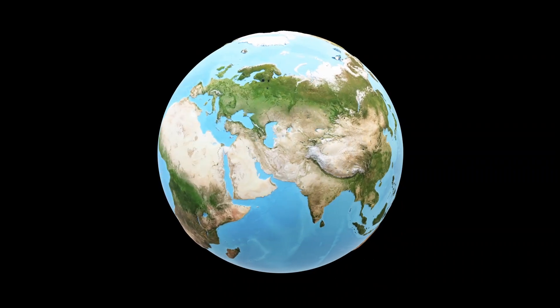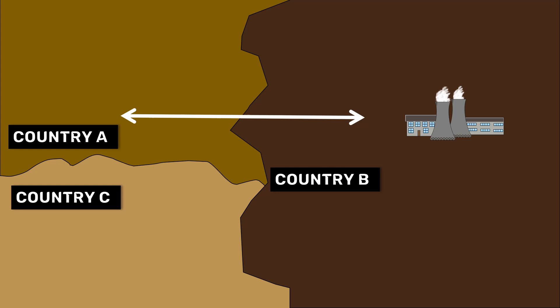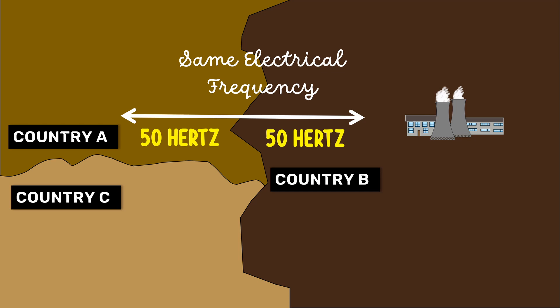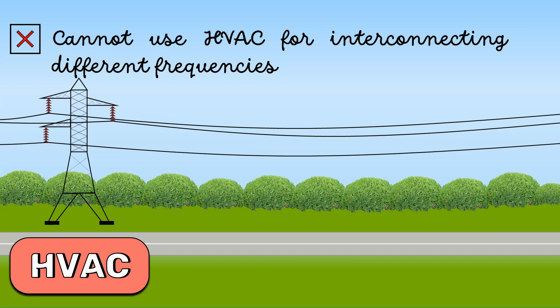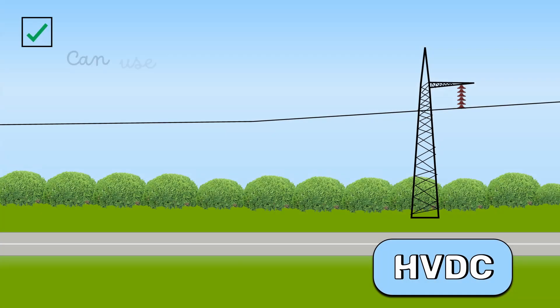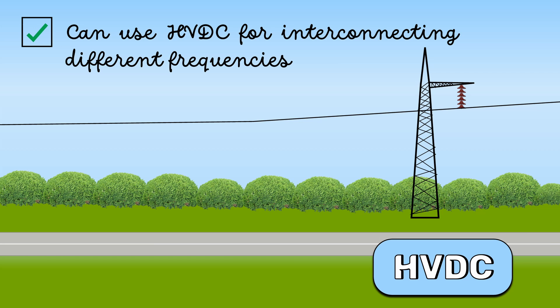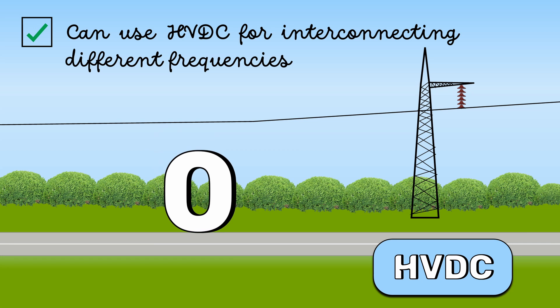Countries that generate surplus electricity trade and share electricity with neighboring countries. The main thing to consider here is that two countries that share electricity should have the same electrical frequencies. But what if their frequencies don't match? We cannot use high voltage AC transmission to interconnect power grids with different frequencies. However, HVDC is very useful in interconnecting power grids with different frequencies, because DC frequency is zero, so we don't have to worry about frequency matching.